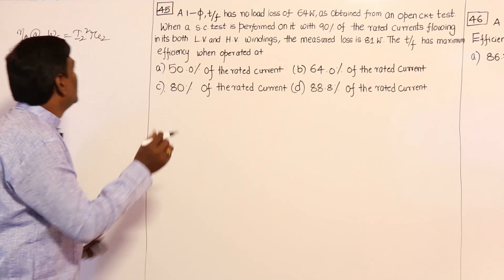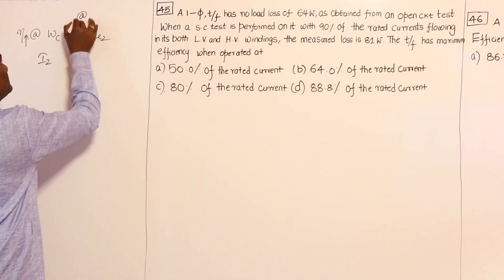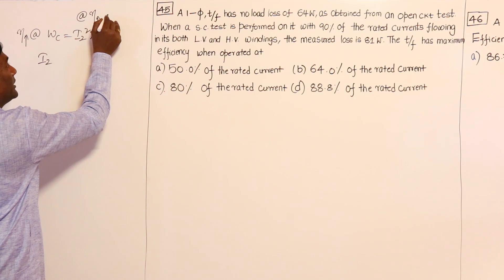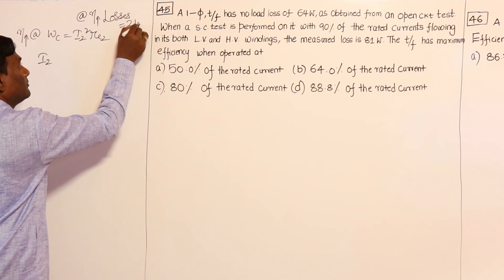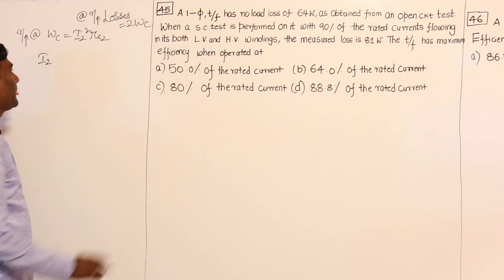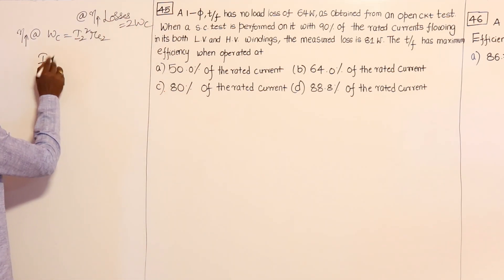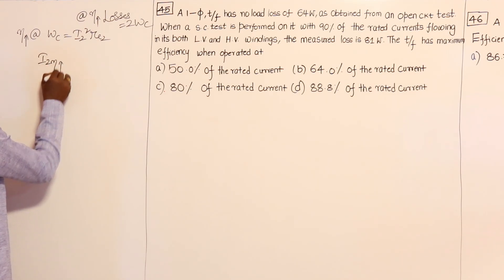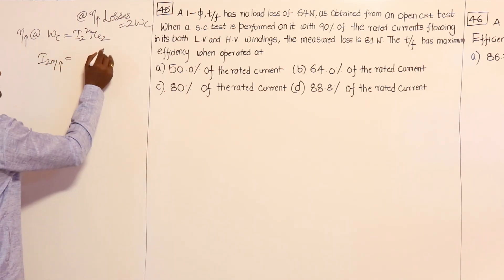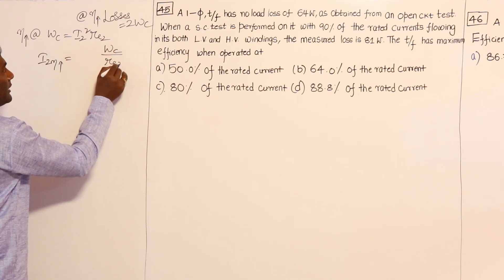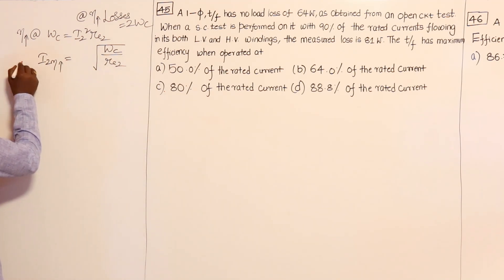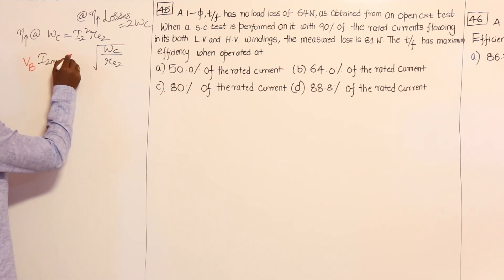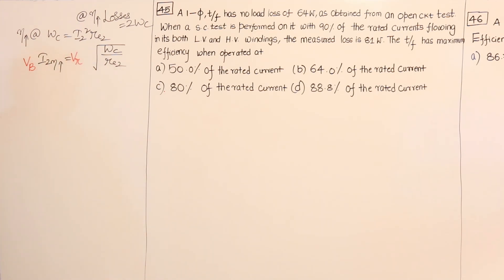At maximum efficiency, total losses equal 2 times core loss. By the equation — core loss equals copper loss — the current I₂ at which maximum efficiency occurs equals the square root of core loss divided by Re₂. Adding rated voltage as the base value, the equation remains the same.